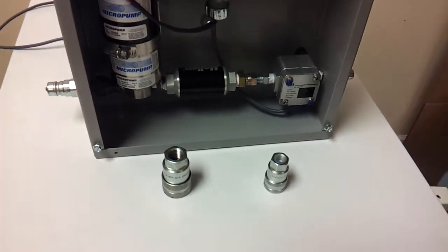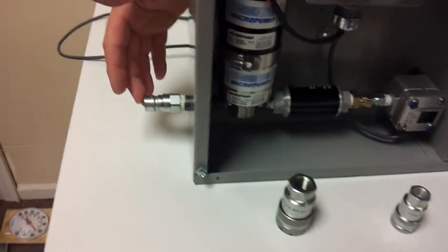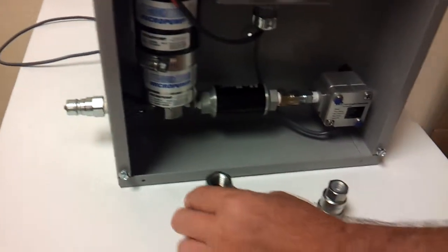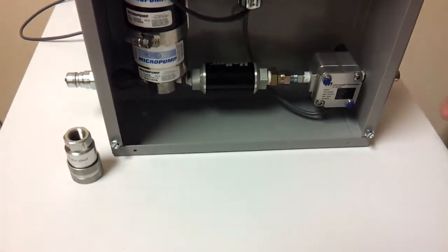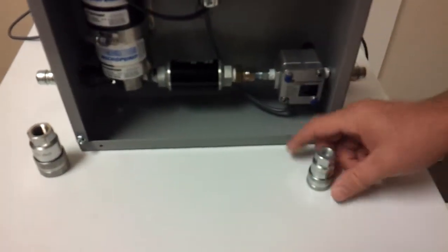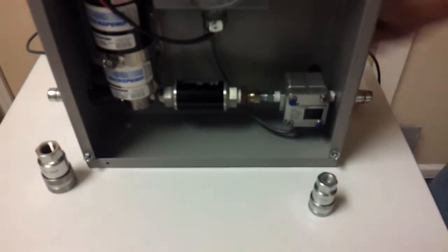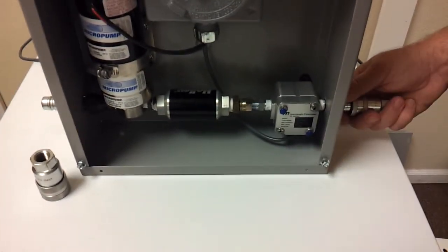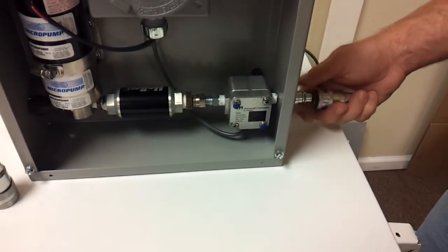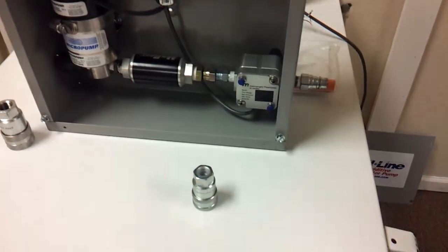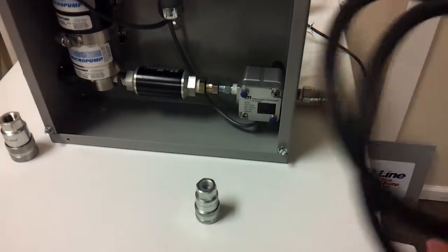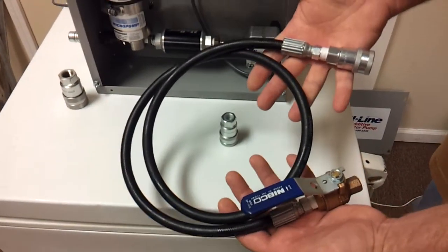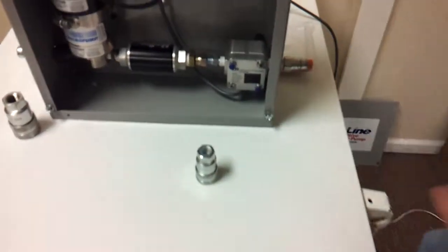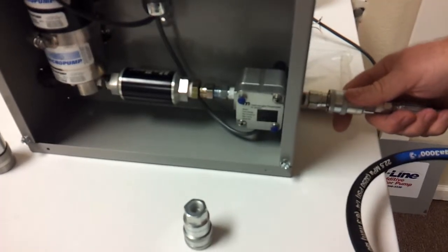As you can see on the pump module, there are typically quick connects. We provide the other side of the quick connects for installation. This quick connect is particularly useful because this is the output, and by having a quick connect there, you can use the calibration hose that we provide and do a quick calibration.